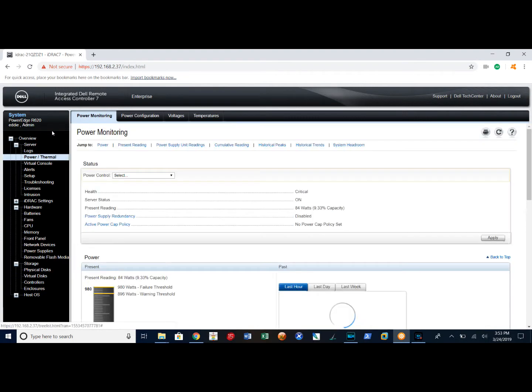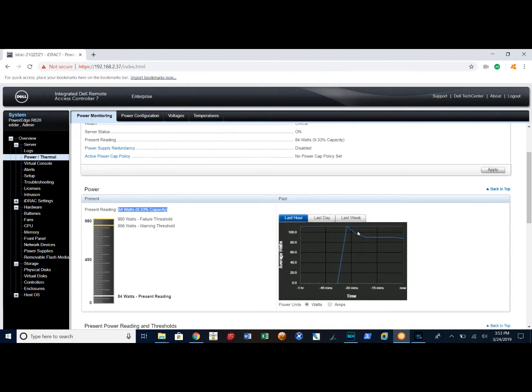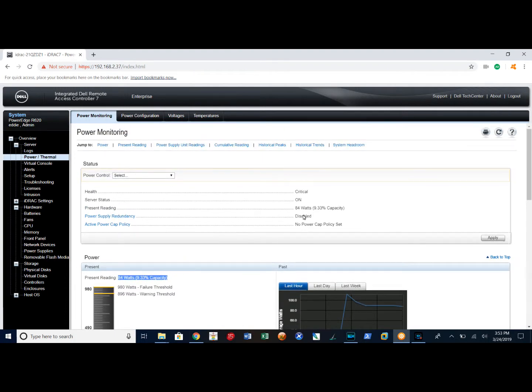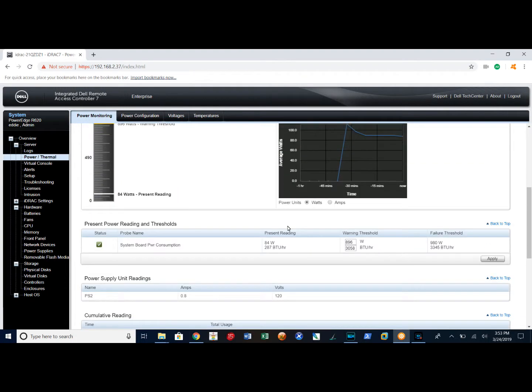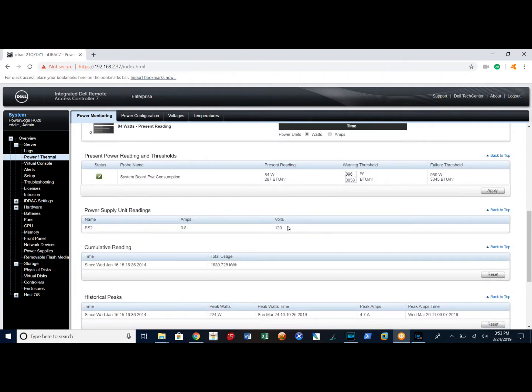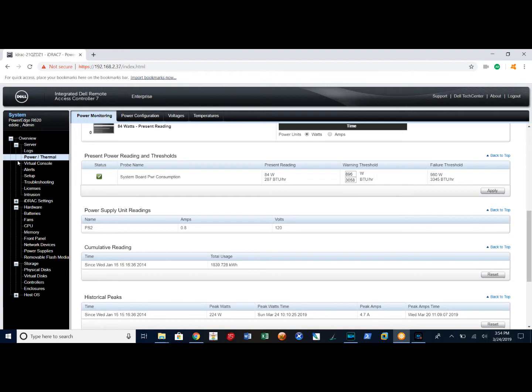Going back here to power, I can see how much consumption the machine is using at this given moment in time. Right now that's 84 watts. It gives me a timeline as well. It tells you BTU per hour 267, gives you a warning threshold and a failure threshold. You can modify these numbers if you like. It gives you peaks as well. You can look at the logs.